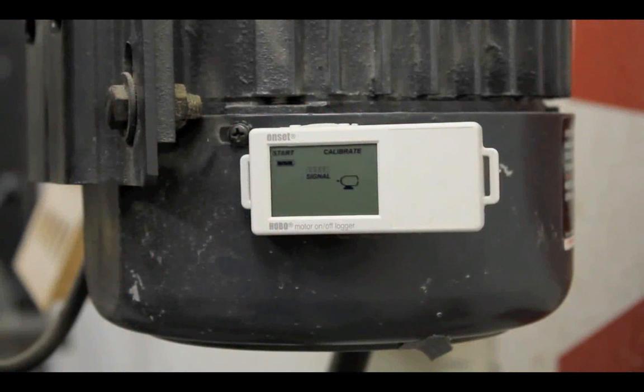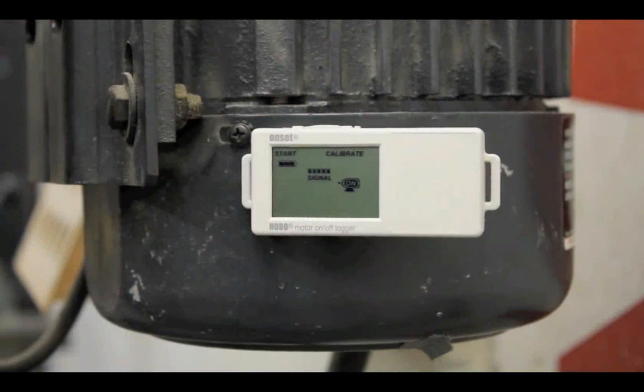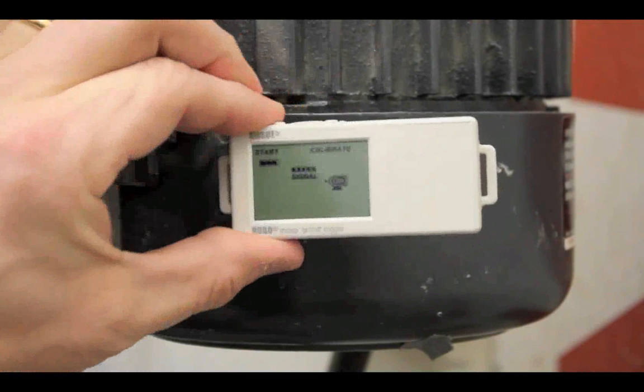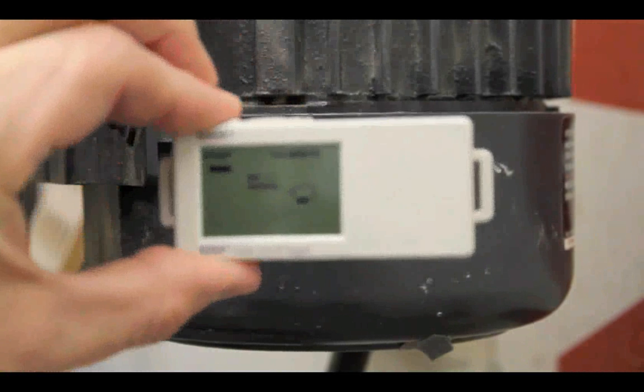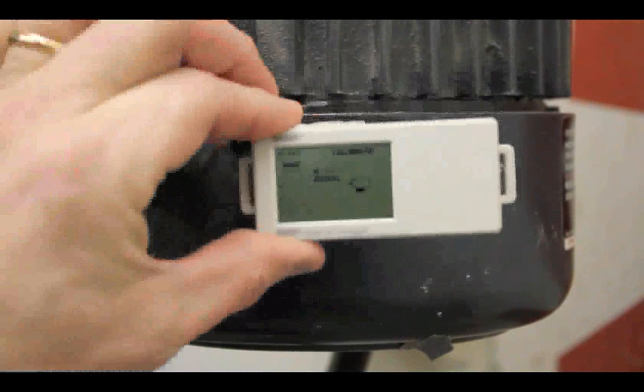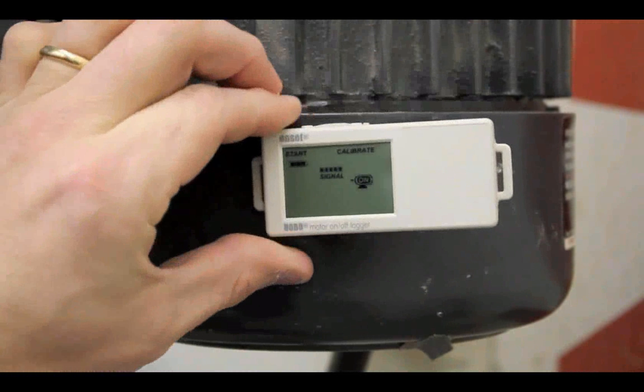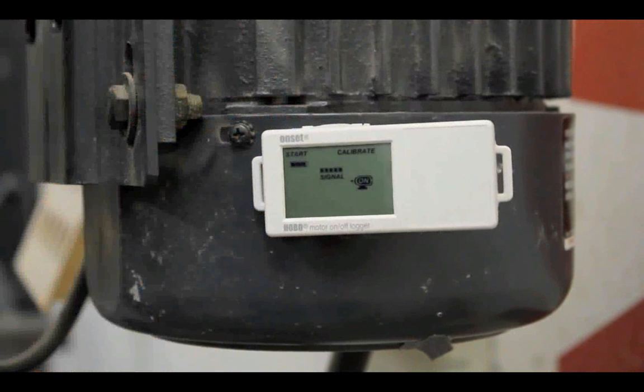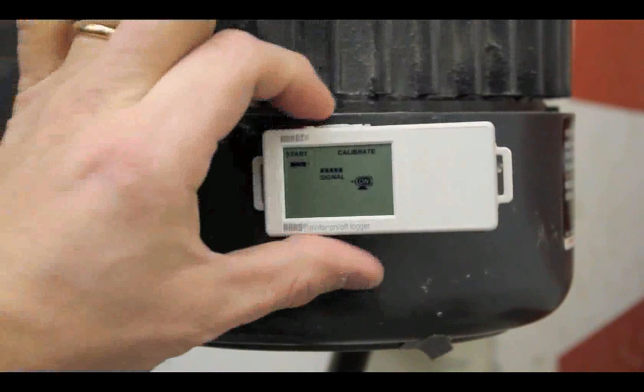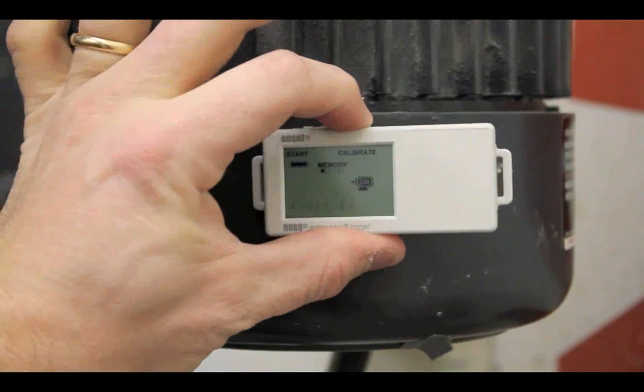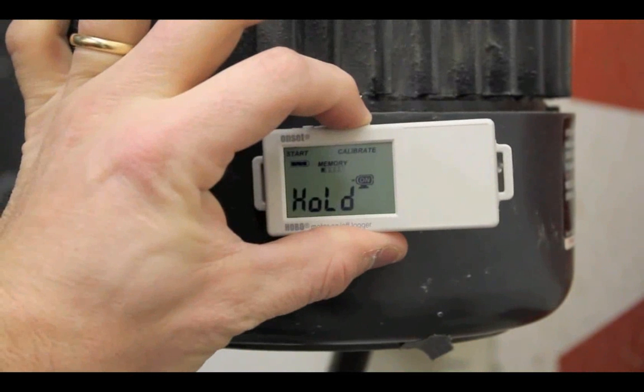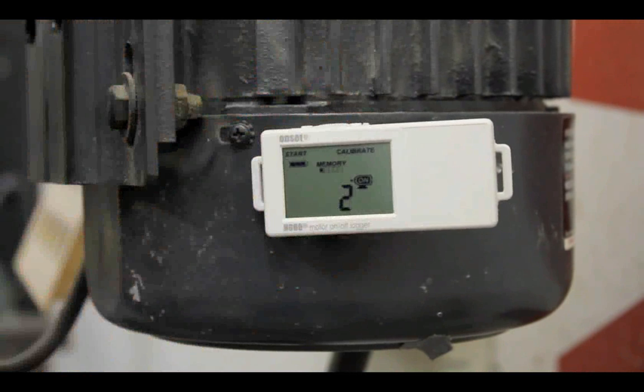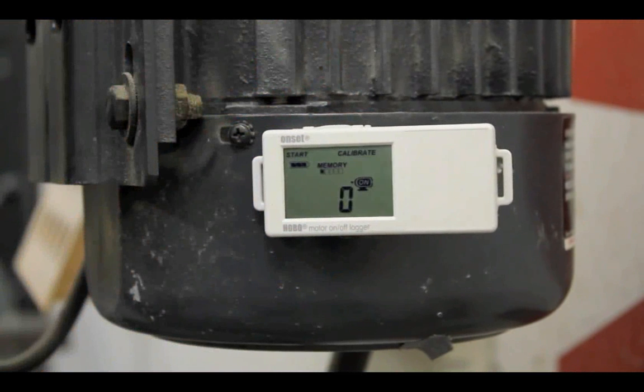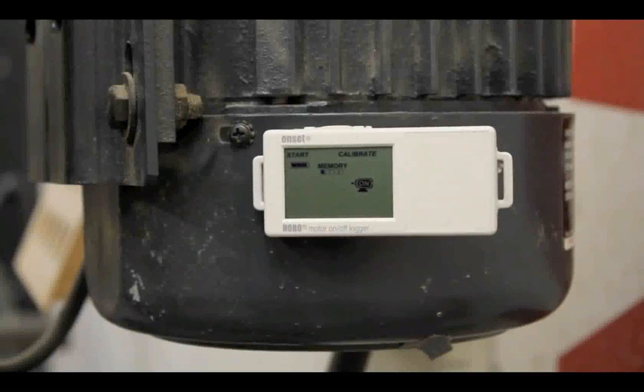We're going to turn on the drill press, and this jumps right up to 5 bars. As you can see, as you remove it from the motor, as the signal strength gets weaker, it'll go down. And then as we get closer, it'll come back up to 5 bars. What we're going to want to do is lock in the 5-bar threshold. So once again, we hold down that right-hand button for 3 seconds. Once it starts counting down, you can let go, and this is going to lock in the threshold. So it'll say auto calibrate pass or fail. In this case, this passed.